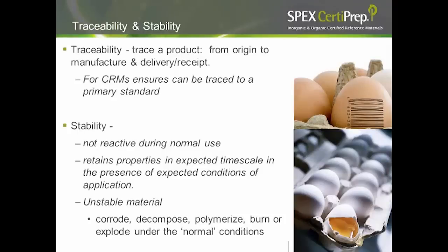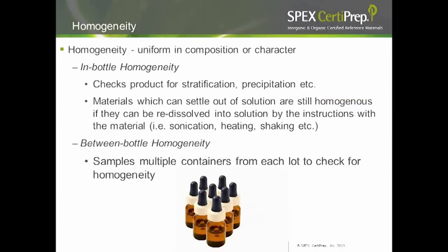Unstable material would corrode, decompose, polymerize, burn, or explode under what would be considered normal conditions. For homogeneity, there are two different ways of determining it: in-bottle homogeneity, which checks for product stratification or precipitation, and between-bottle homogeneity, where a manufacturer makes a large lot of material bottled into separate units and a subset of five to ten bottles is sampled to check for homogeneity across the lot.